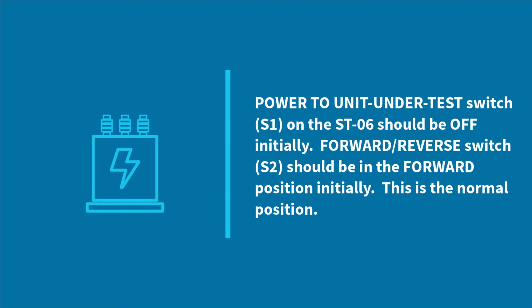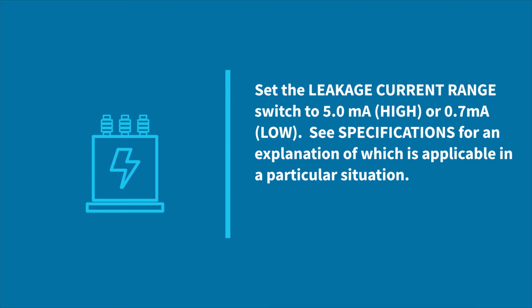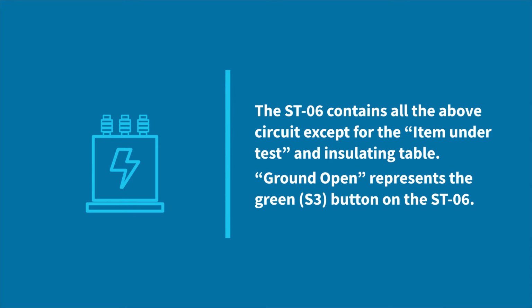Power to unit under test switch S1 on the ST06 should be off initially. Forward reverse switch S2 should be in the forward position initially. This is the normal position. Set the leakage current range switch to 5 milliamps high or 0.7 milliamps low. See specifications for an explanation of which is applicable in a particular situation. The ST06 contains all the above circuit except for the item under test and insulating table. Ground open represents the green S3 button on the ST06.